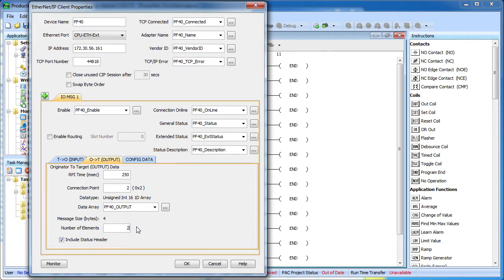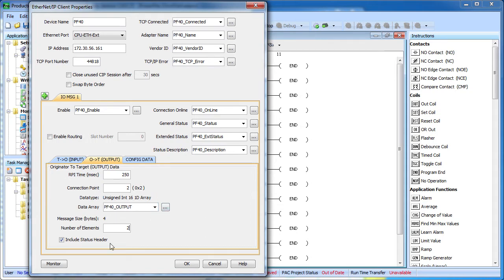Some devices require a 4 byte status header be sent with the output data. The PowerFlex is one of those devices so we need to make sure that this box right here is checked. Perfect.